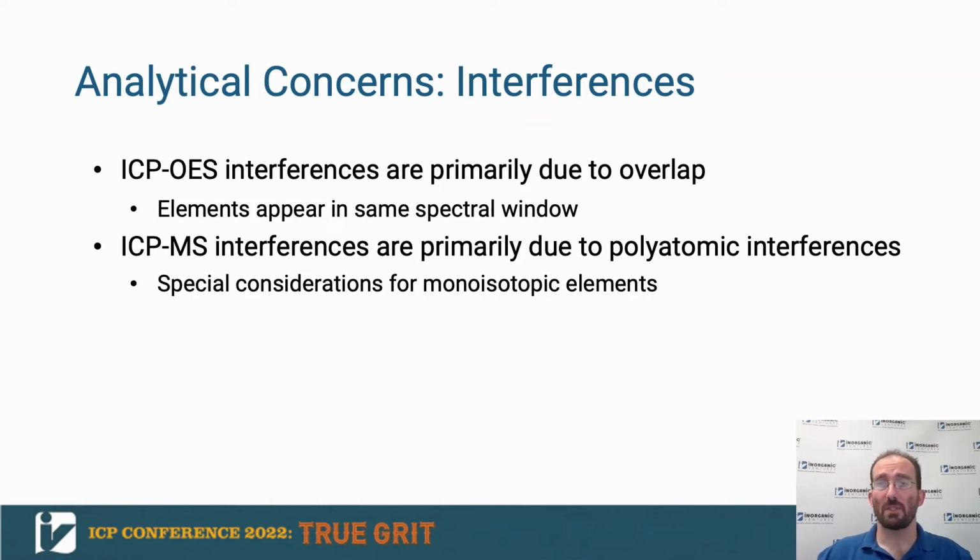The easiest example to give for mass spec, not just for the EPA methods, but mass spec in general, is at mass 40. This at first glance would seem like an ideal place to check for calcium until you take into consideration that your argon gas will also be showing up at mass 40. The interactive periodic table on our website will list several interferences for each element that will not only help you make good line or isotope choices, but can also give you guidance on what your interferences may be.